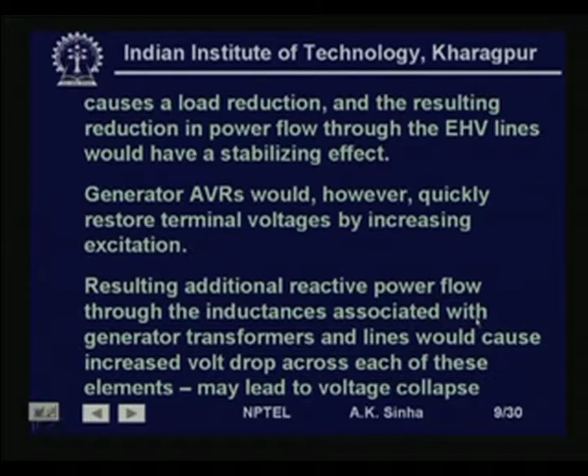So, this is what is going to happen, because now the voltages have increased, the loads will increase, and that means more power flow will take place on the lines, and this will result in more VAR losses on the line, because the line has large inductance and the current flows through that. So, you are going to have more VAR losses on the lines, and this will cause increased voltage drop on each of these lines.